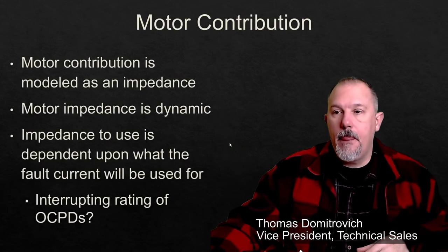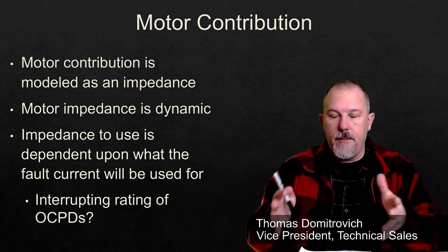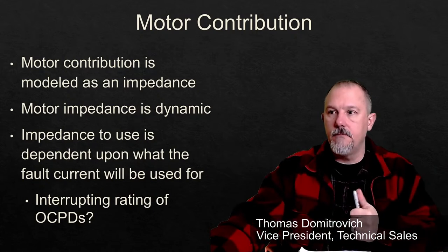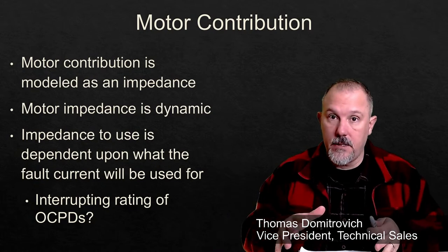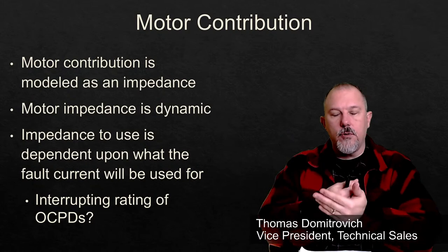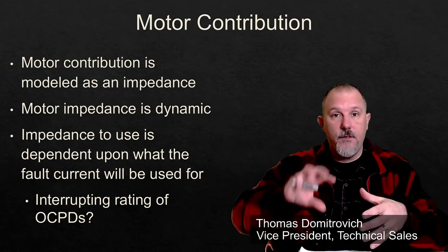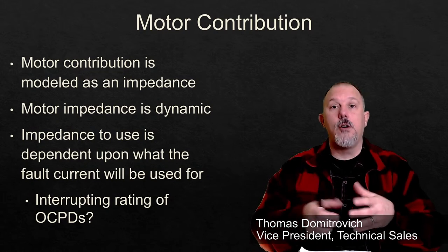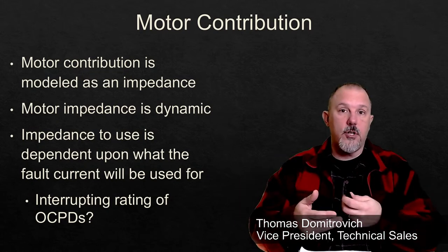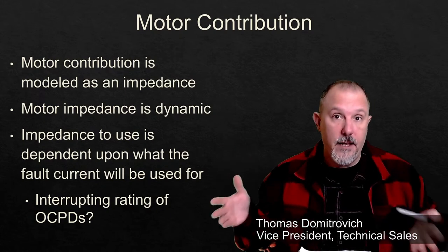All right, so your motor contribution, I have to basically model that motor as an impedance, and it's a dynamic impedance. So the impedance of a motor will change. The moment a short circuit occurs, it turns into a generator because it's got the back EMF. You've got the rotating fields going on. The inertia of that motor is going to keep moving, and then depending upon what you're driving will tell you how long it's going to hang in there.